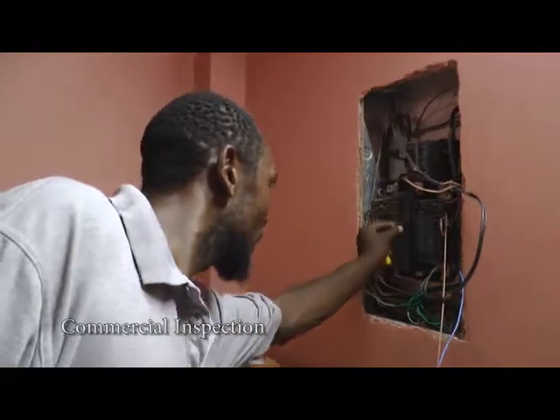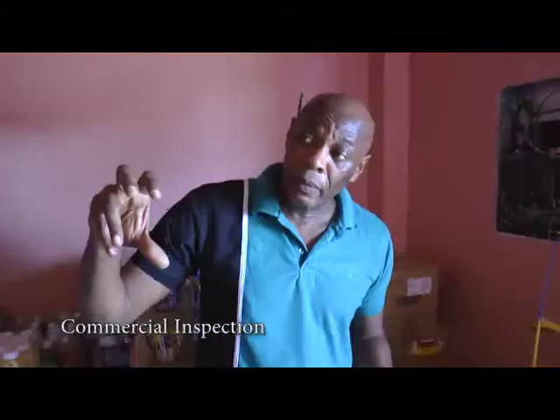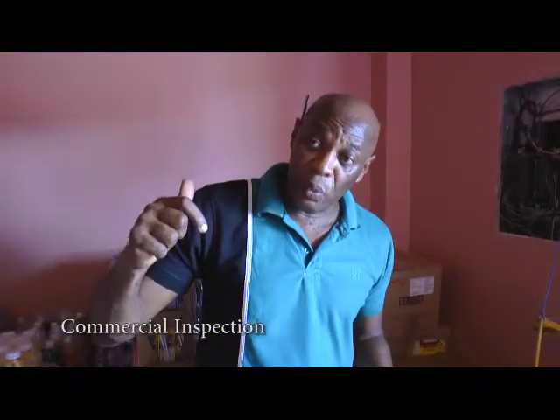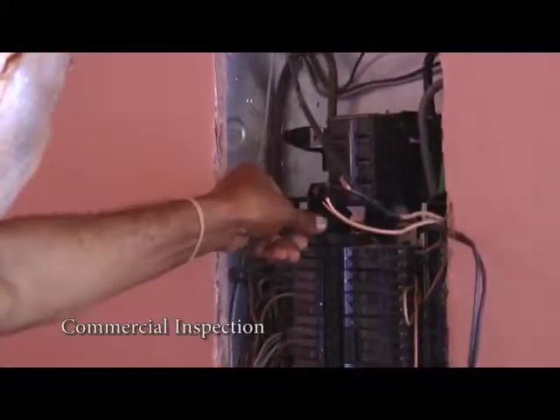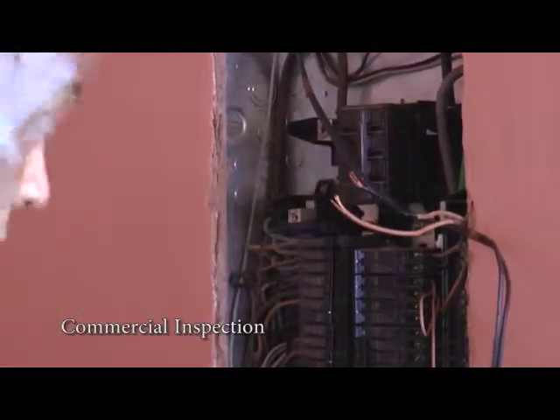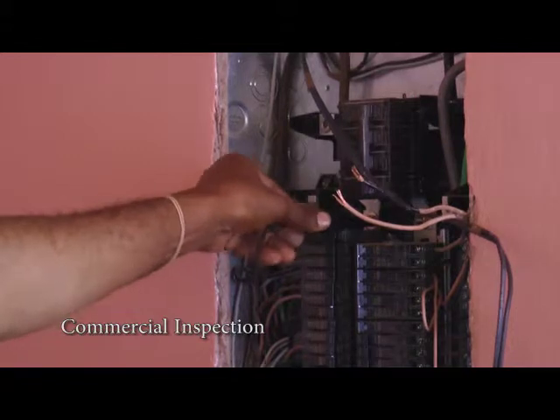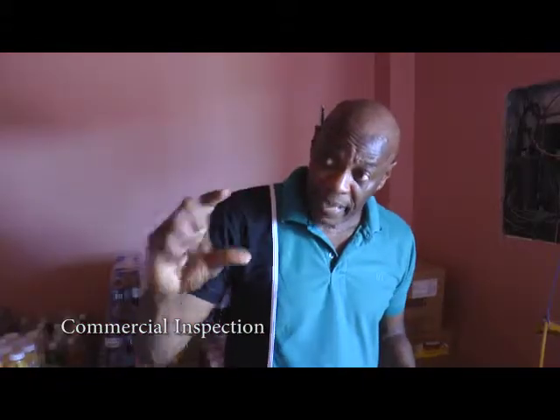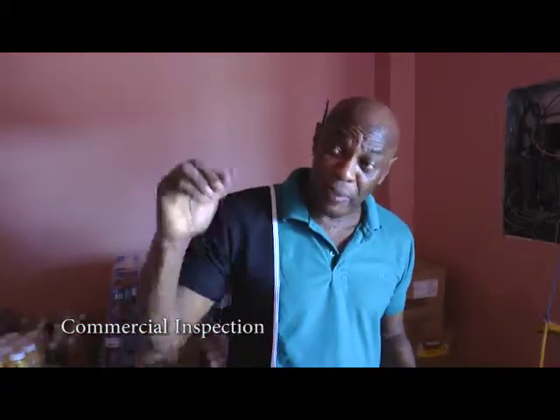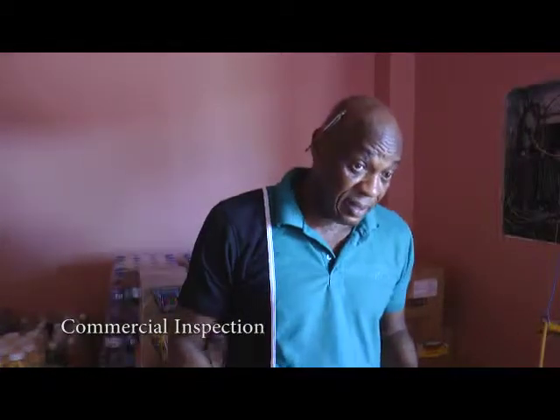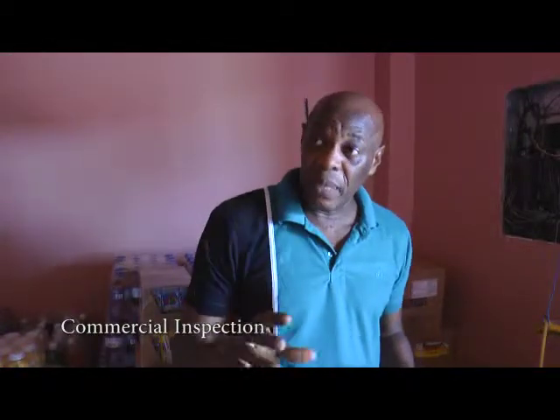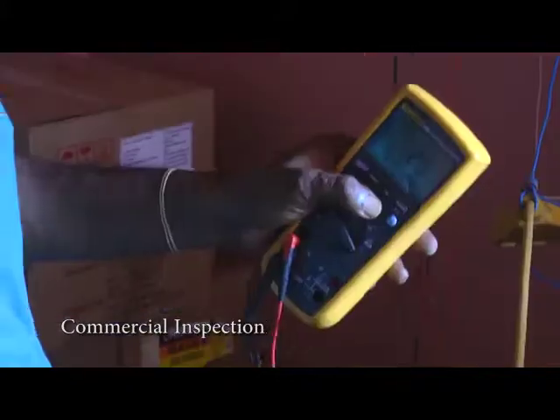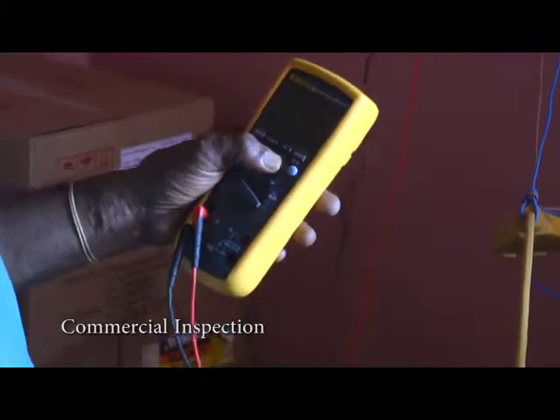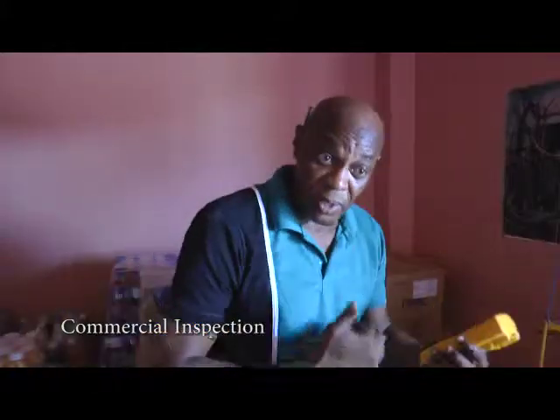The regulation we have for commercial buildings, at 115 volts, which is how most lighting is wired, we don't accept more than 8 lights on a circuit. If it's domestic, we accept not more than 12. But of course, all of that is subject to how much current is on the circuit. The inspector, or the inspectorate, can use discretion where that is concerned.